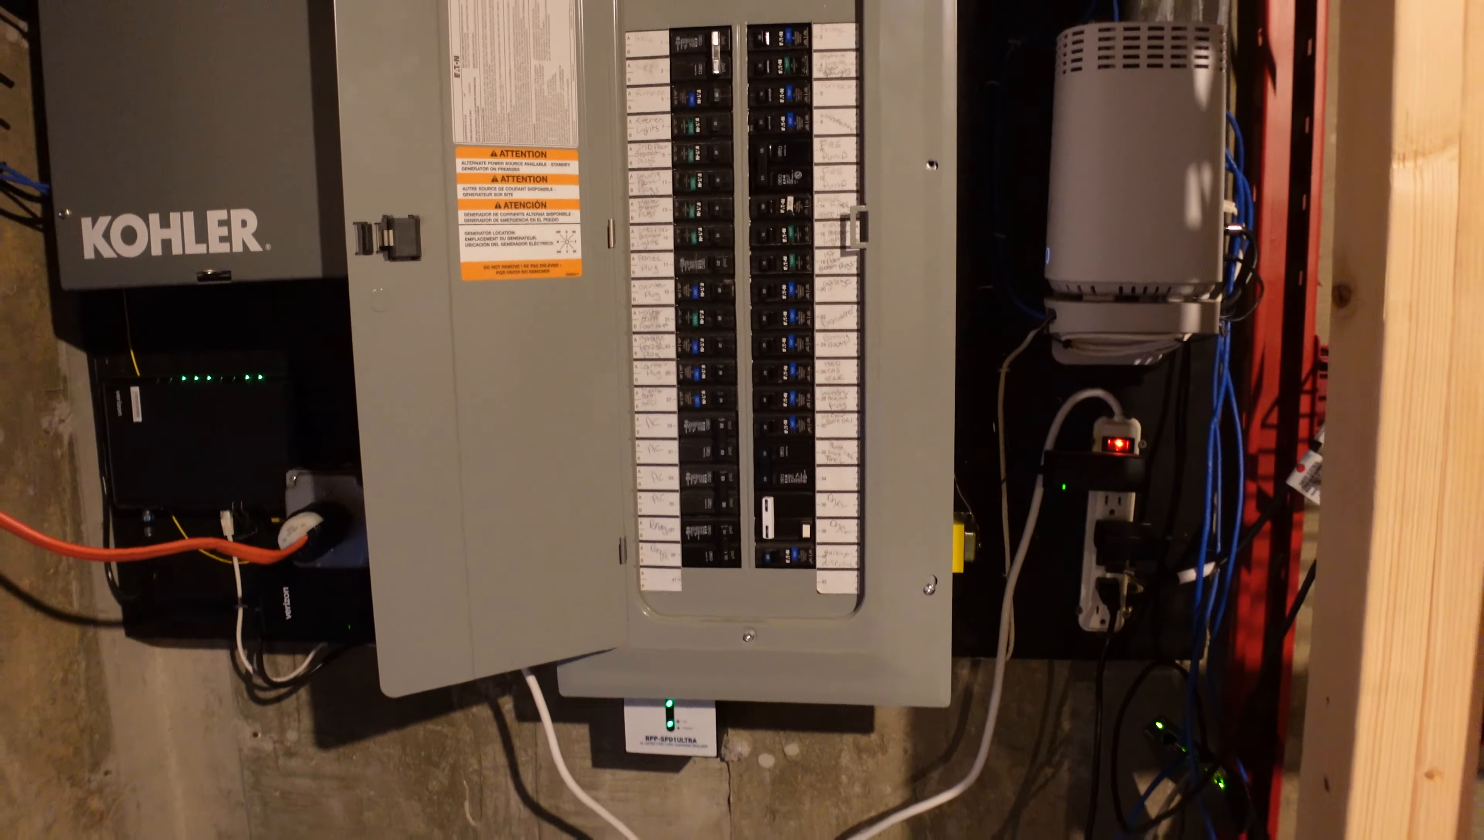So this right here is a 125-amp main lug subpanel. It has eight slots for two-pole breakers, so I could put four two-pole breakers in here. I'm probably going to put like three 20-amp and one 30. If I'm not mistaken, that's probably what I'm going to do. I'm not going to utilize all the amps in this thing. You want to try to stay within like 80%, so around 80 amps is going to be the max I would ever go on this.